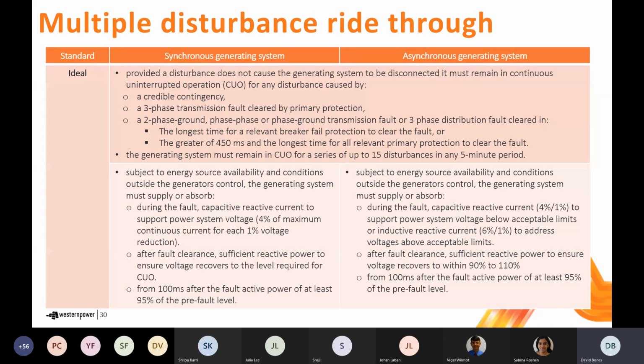So if that was to happen, your generating system, if it's meeting the ideal standard, will be able to maintain continuous uninterrupted operation. Furthermore, there's requirements specified in the bottom of the page talking about the amount of reactive current injection that needs to be provided during the fault and after the fault is cleared to recover voltage. And you can see here that we're talking about fairly significant amounts of reactive current contribution. So we're talking about 4% of the maximum current contribution for every 1% reduction in voltage. And a similar requirement there for asynchronous generating systems. The asynchronous generating system requirements also provide or specify a requirement for inductive reactive current that would be provided to reduce voltages should they be too high.